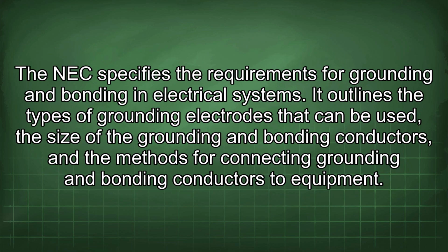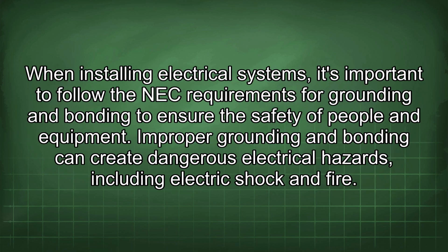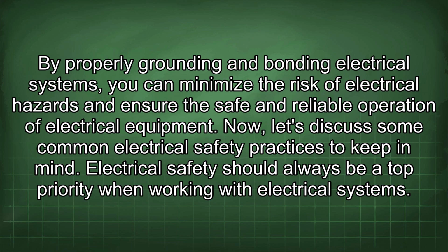The NEC specifies the requirements for grounding and bonding in electrical systems. It outlines the types of grounding electrodes that can be used, the size of the grounding and bonding conductors, and the methods for connecting grounding and bonding conductors to equipment. When installing electrical systems, it's important to follow the NEC requirements for grounding and bonding to ensure the safety of people and equipment. Improper grounding and bonding can create dangerous electrical hazards, including electric shock and fire. By properly grounding and bonding electrical systems, you can minimize the risk of electrical hazards and ensure the safe and reliable operation of electrical equipment.